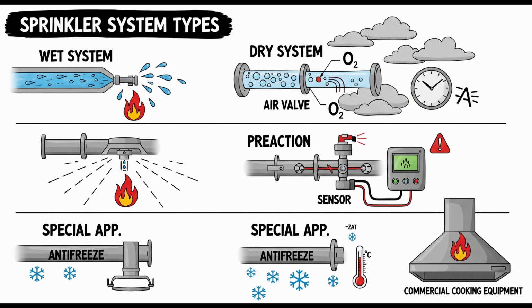Why is that? To ensure adequate water flow and pressure is available across the entire area threatened by that single fire. Subdividing could potentially starve one side if the other activated first or required more flow. Makes sense. Pipe and fittings used on the exterior must be corrosion resistant. Obviously, yes. They're constantly exposed to weather, rain, sun, potentially salt spray in coastal areas, or industrial pollutants. Corrosion resistance is critical for longevity and reliability.